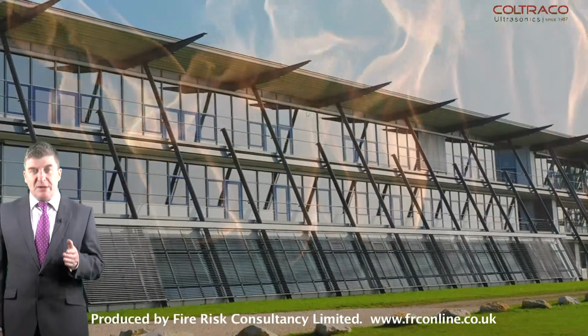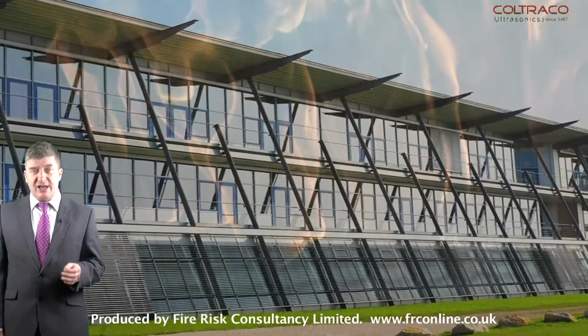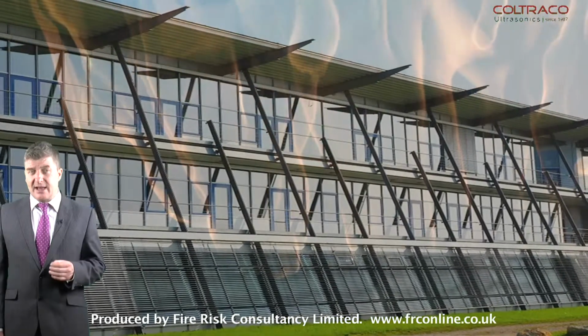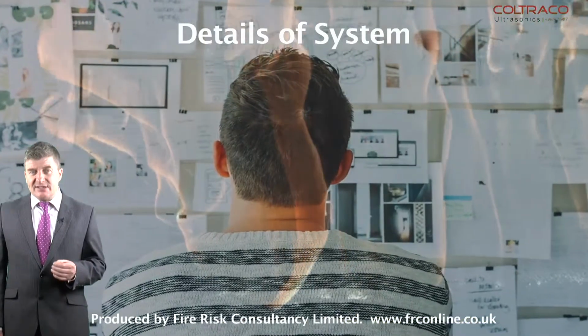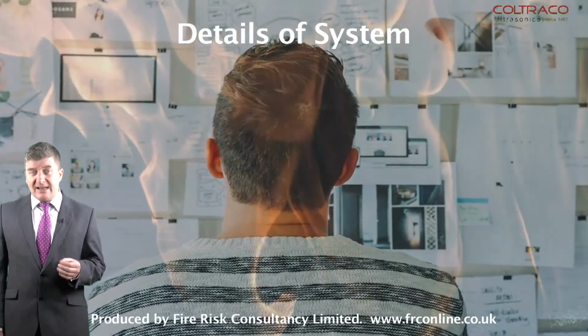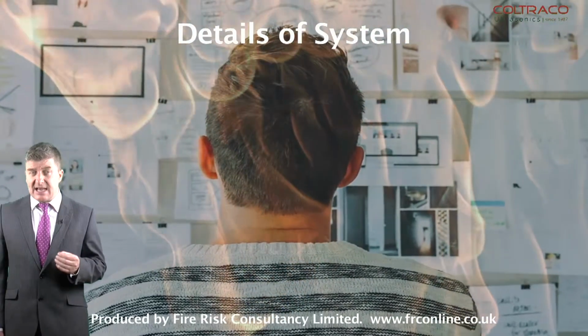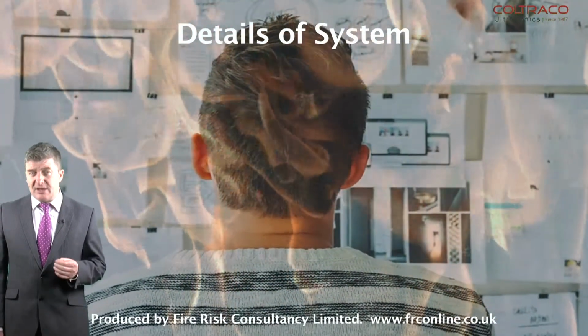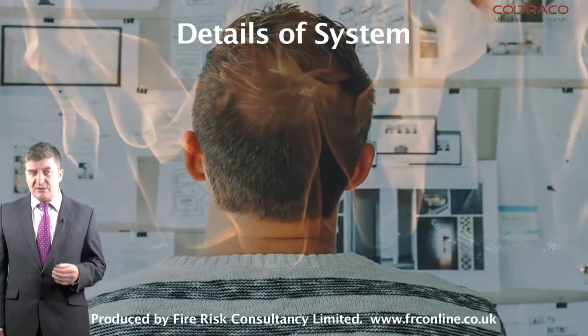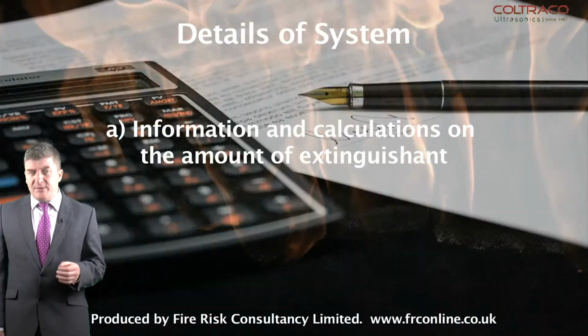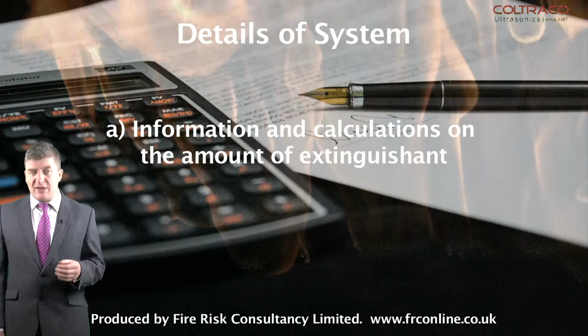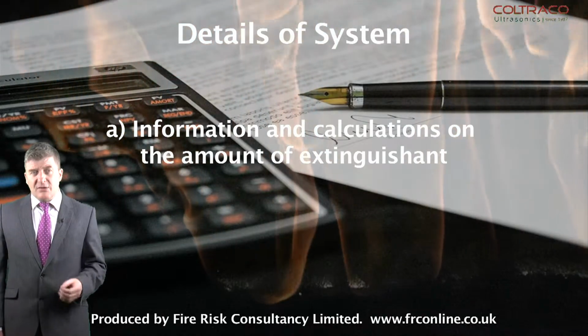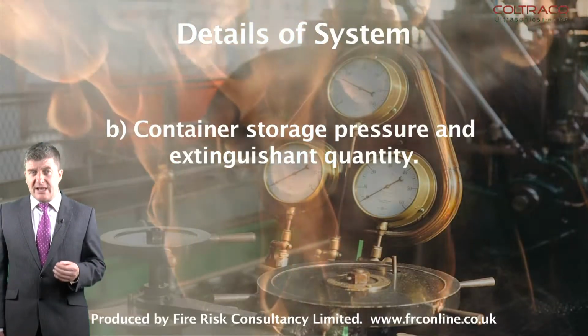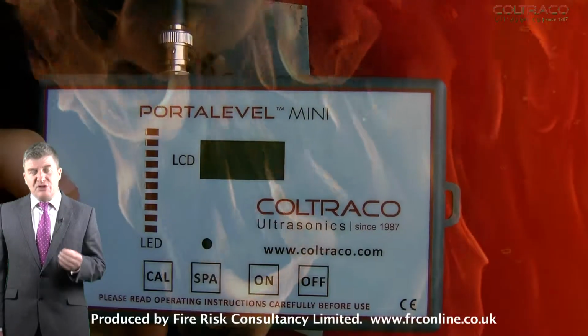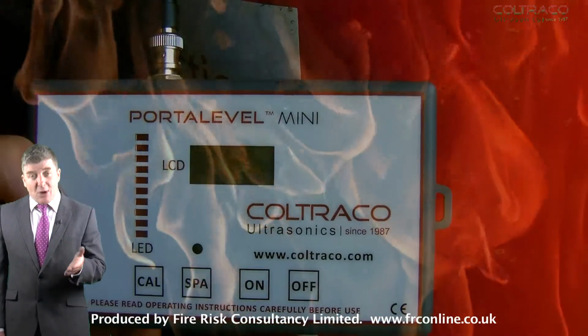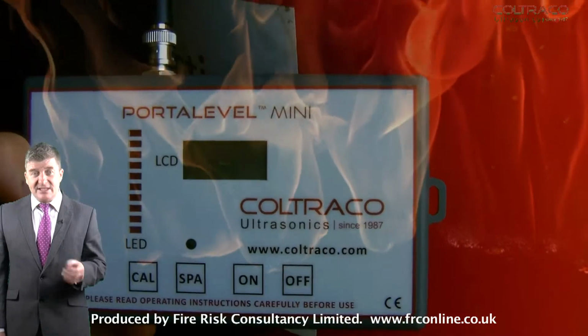So the risk to a building structure aging and generating leak sites is recognised. For engineered systems, the end user shall be provided with the manufacturer's system design and maintenance information. Details of the system shall include the following: the information and calculations on the amount of extinguishant, the container storage pressure and extinguishing quantity.